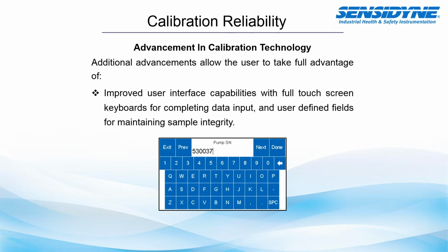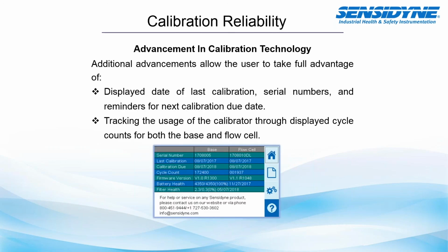Some additional advancements include user interface. So now you have the capability with some newer technologies to actually have full touchscreen keyboards to input those user-defined fields that you want to have in your calibration log. Additionally, newer instruments are able to display the date of last calibration, the serial numbers for your calibration device, and the next calibration due date, which are all key elements of what you'd want to see in a calibration report.